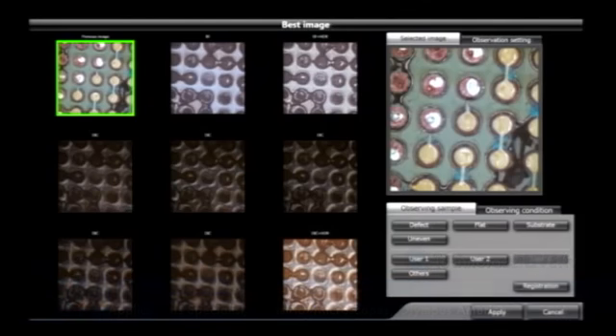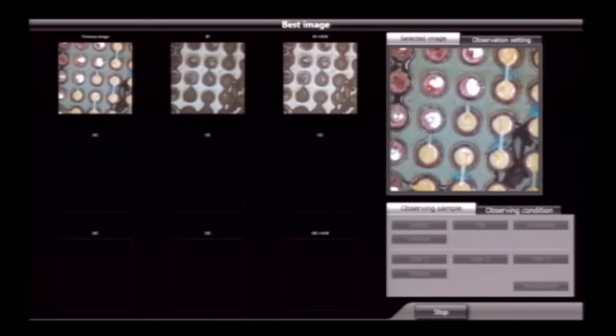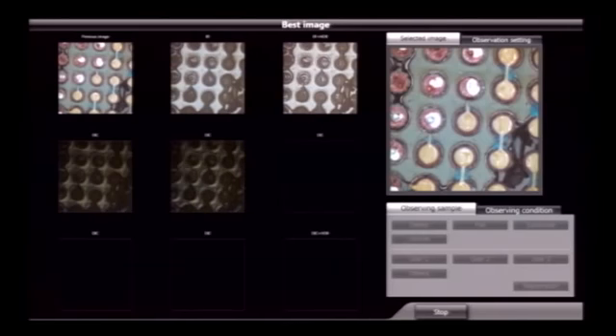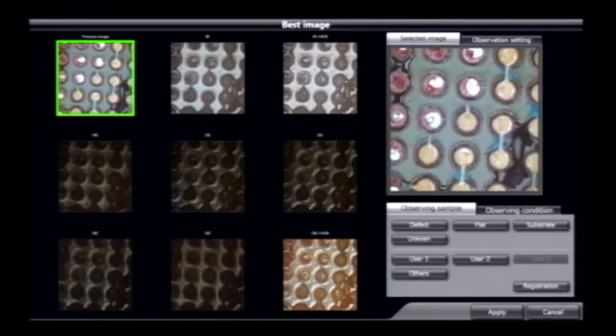The system's meant for ease of use, though. An operator can come up, put their sample on very quickly, and they want to get their best image. The way to do that, with our built-in best image function, they select what they're running, maybe a flat type sample, and the tool will set up a whole bunch of pre-sampled images and switch between observation methods automatically. So it's showing you on this side, this is a preview of what these different observation types would look like, and then you're just going to simply select the one that you feel is closest to what you're trying to do. So you have our bright field image, we have DIC images, and we also have some of our observation techniques like DIC with HDR, high dynamic range.